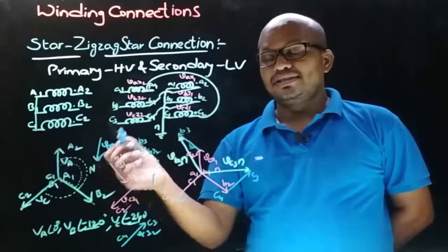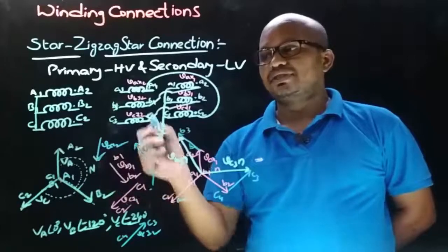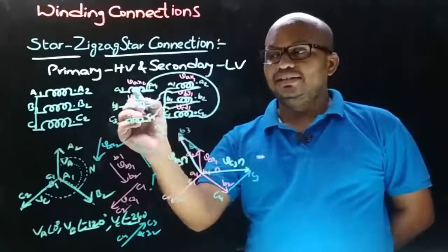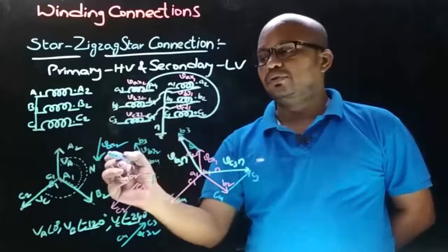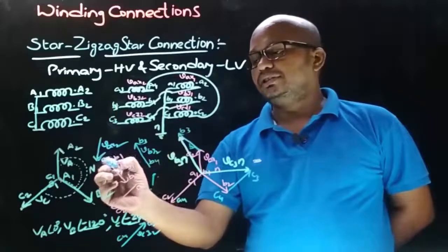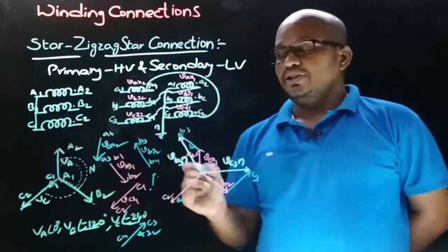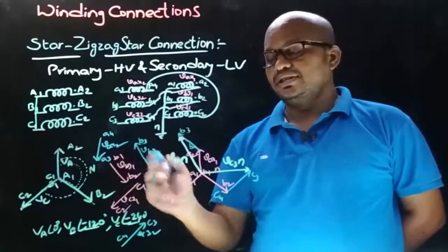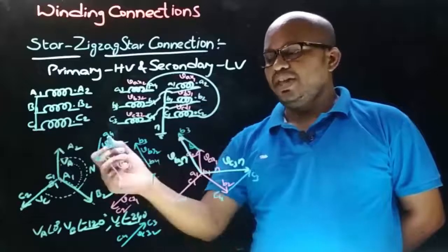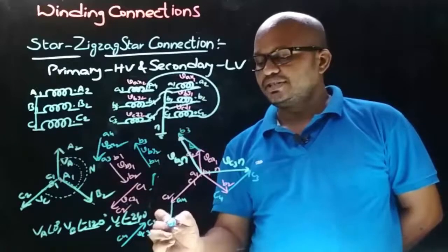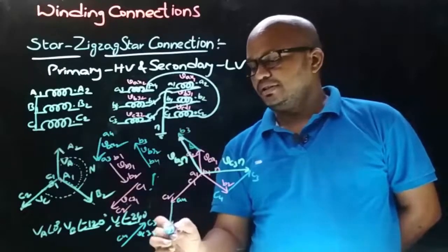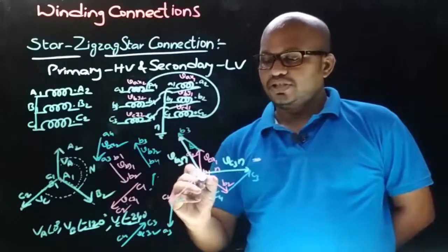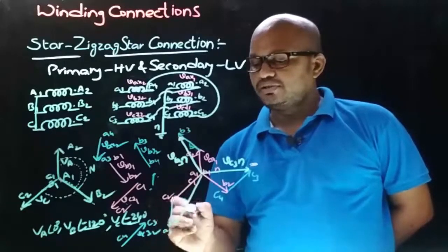Observe that the primary side consists from dot end and the secondary side consists from non-dot end, means the direction of secondary side VAX2 phasor is opposite to primary side VA phasor. And now let's decide the terminals of secondary side VAX2 phasor. Terminals are A3 and A4 and the connection is from non-dot end. Therefore, arrow end will be A3 and other end will be A4. Now draw this secondary side VAX2 phasor such that C2 will have A4 connection, means like this. This end is A3.